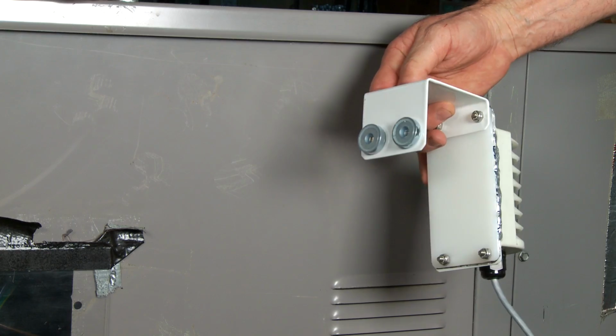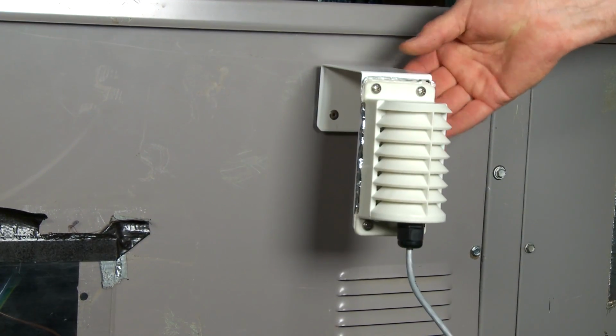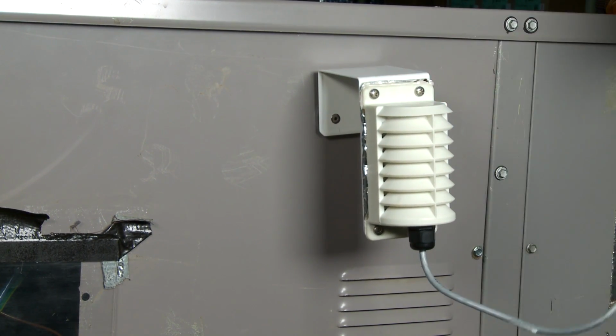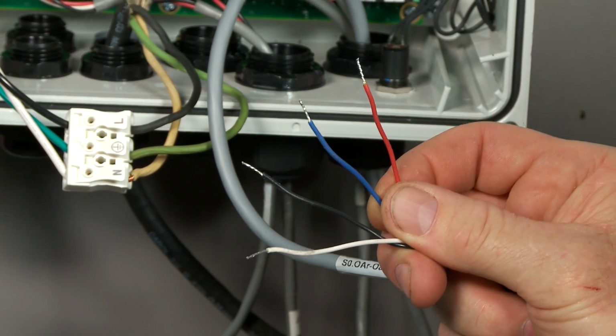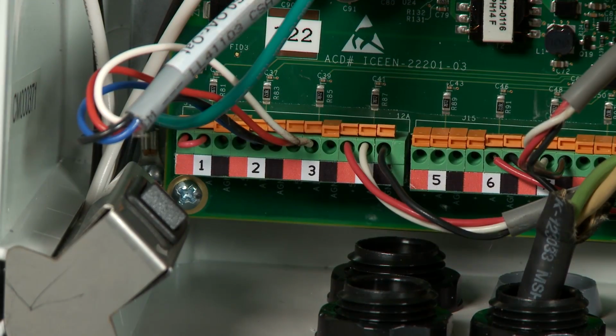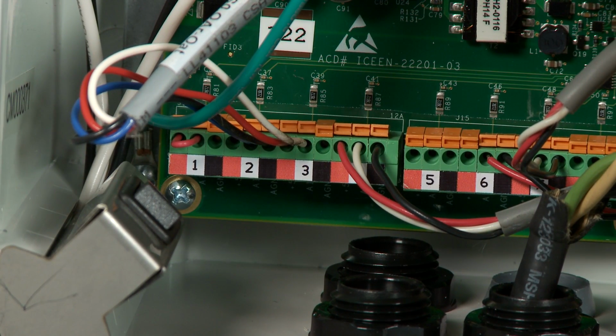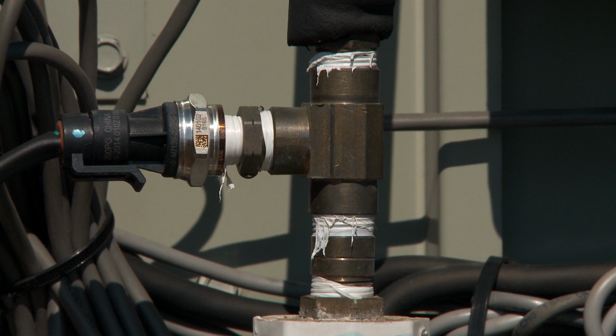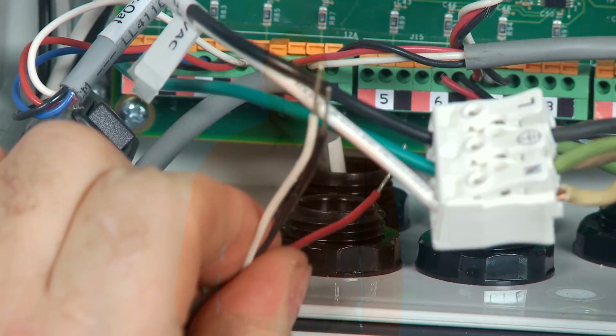After that, attach the weather sensor package using the included magnetic mount on a side of the unit that will not receive direct sunlight. Most often, a northern-facing side works best. At this time, the water pressure transducer also needs to be installed. You will need a 1/4 inch NPT connection to the incoming water line in order to install the transducer. Connect the sensor leads through a cable grip on the controller box and attach to the board.